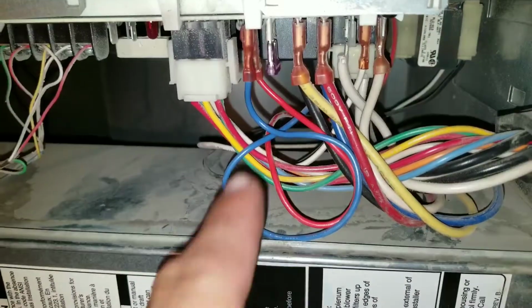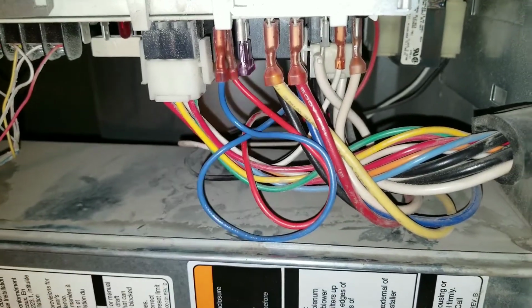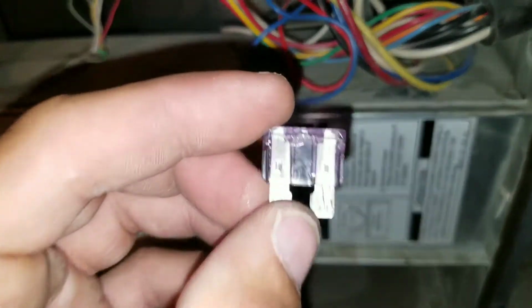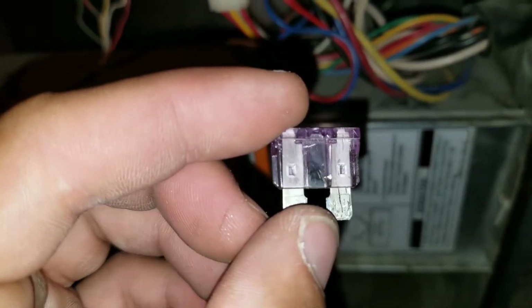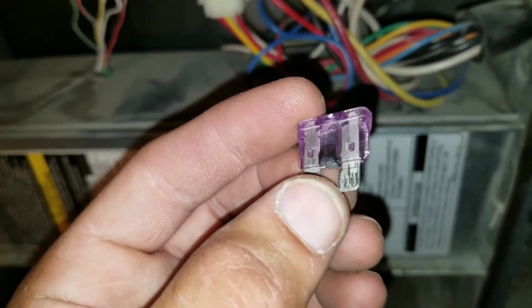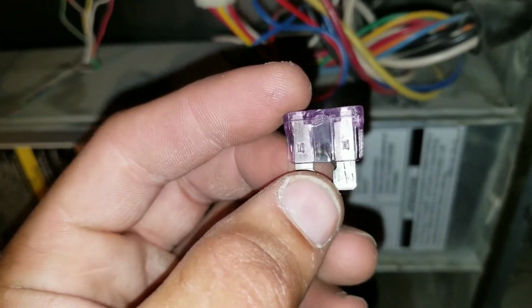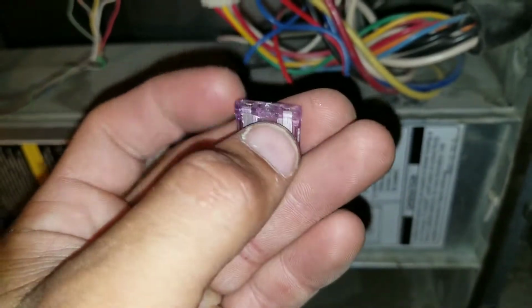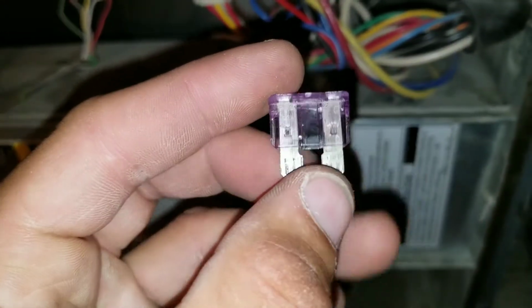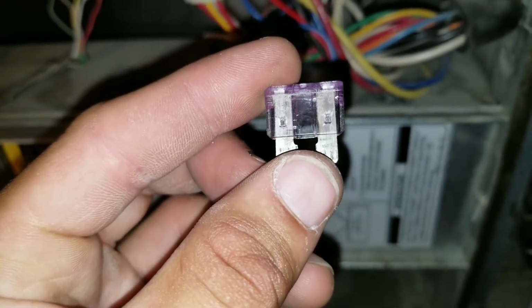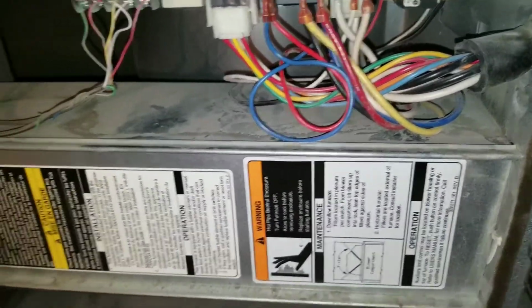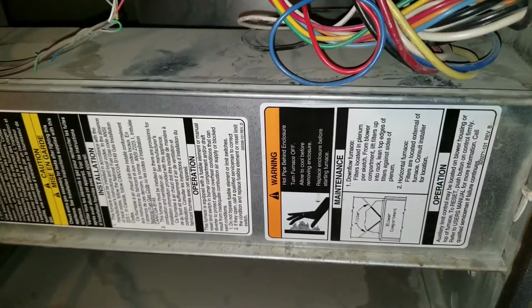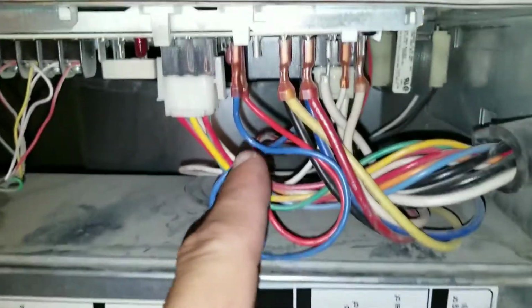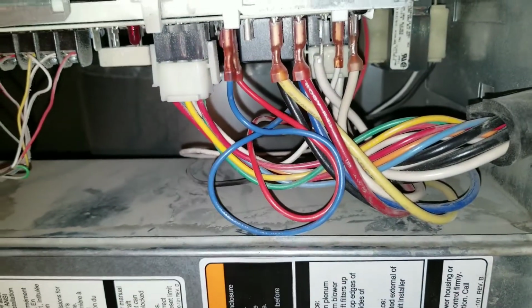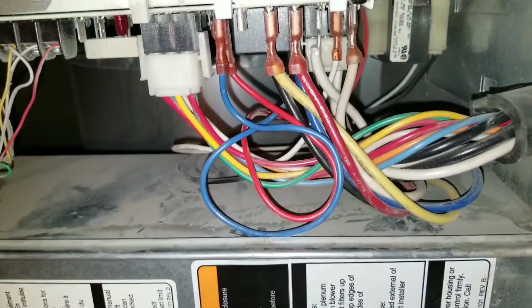Now what I'm going to do is we're going to inspect our fuse. So here I've removed the fuse, and you can see that the fuse blew. You can see the black in the middle, and then my little coil going down popped. At this point what I'm going to do is I'm going to plug back in the power going to my furnace, and then I want to check my multimeter where the fuse was, and I want to see what kind of voltage we have coming in to our board.